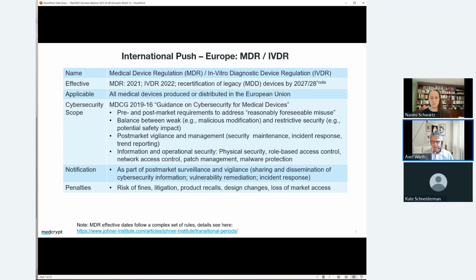So MDR, IVDR is the legal background, is not specific to cybersecurity. It talks about safety and all aspects of medical device management. But again, MDCG 16 is specifically the cybersecurity interpretation of the laws. It talks about pre and post market requirements that need to be addressed, the consideration around reasonably foreseeable misuse, things like hackers and malware on devices, for example. It does state, interesting enough, that there needs to be a balance between too weak security, which could lead to malicious modification of a device on one hand, but then also too restrictive security on the other hand, that could potentially impact patient safety through, for example, delayed data access or delayed logon of a clinical care provider.